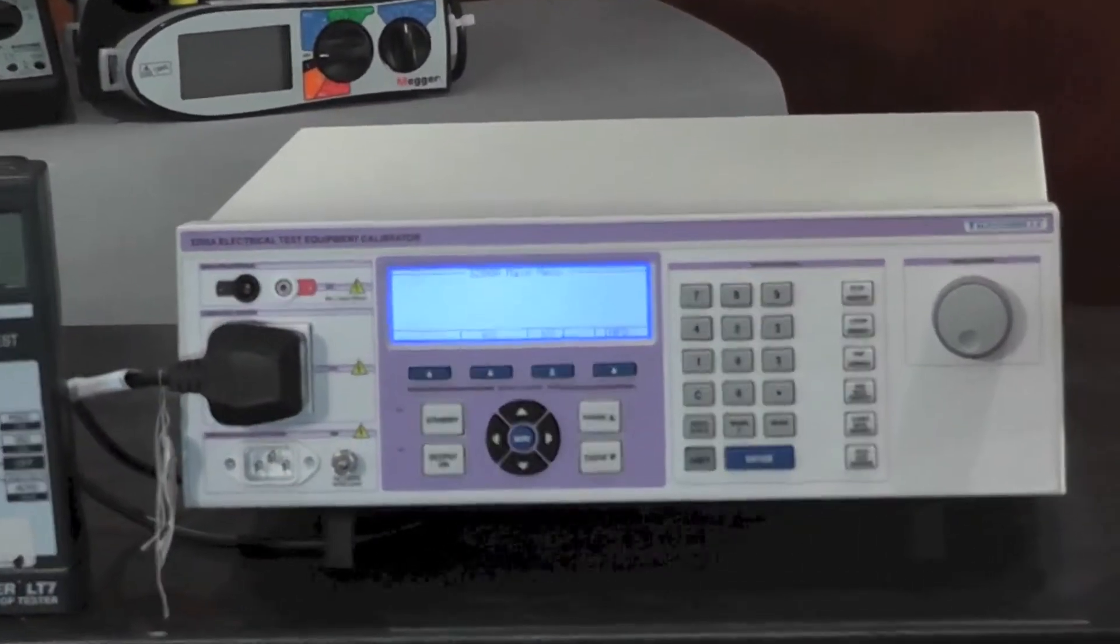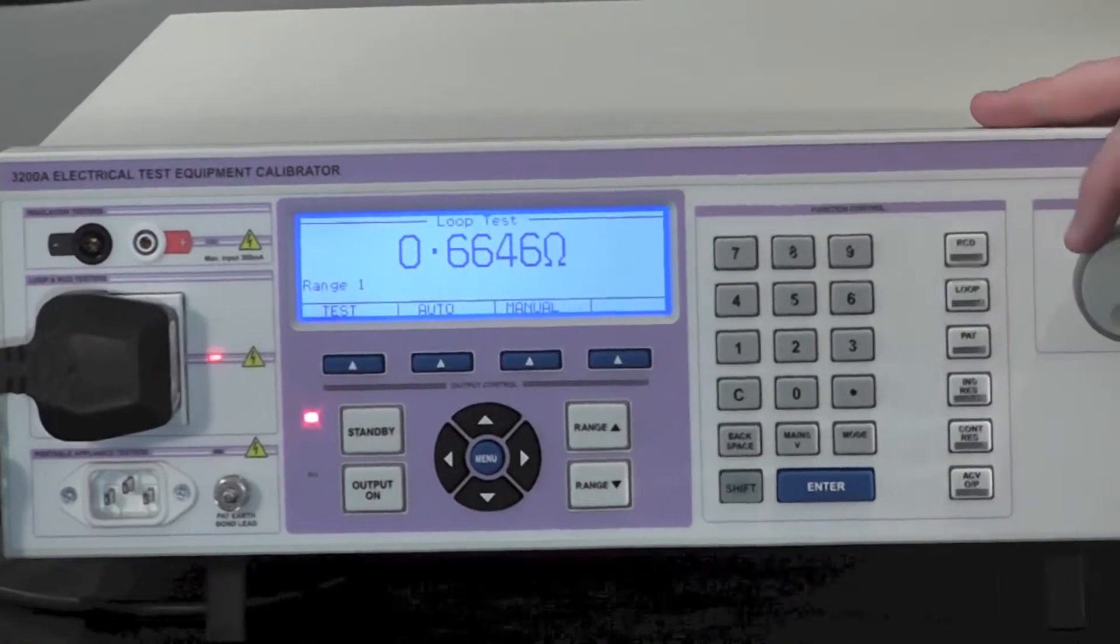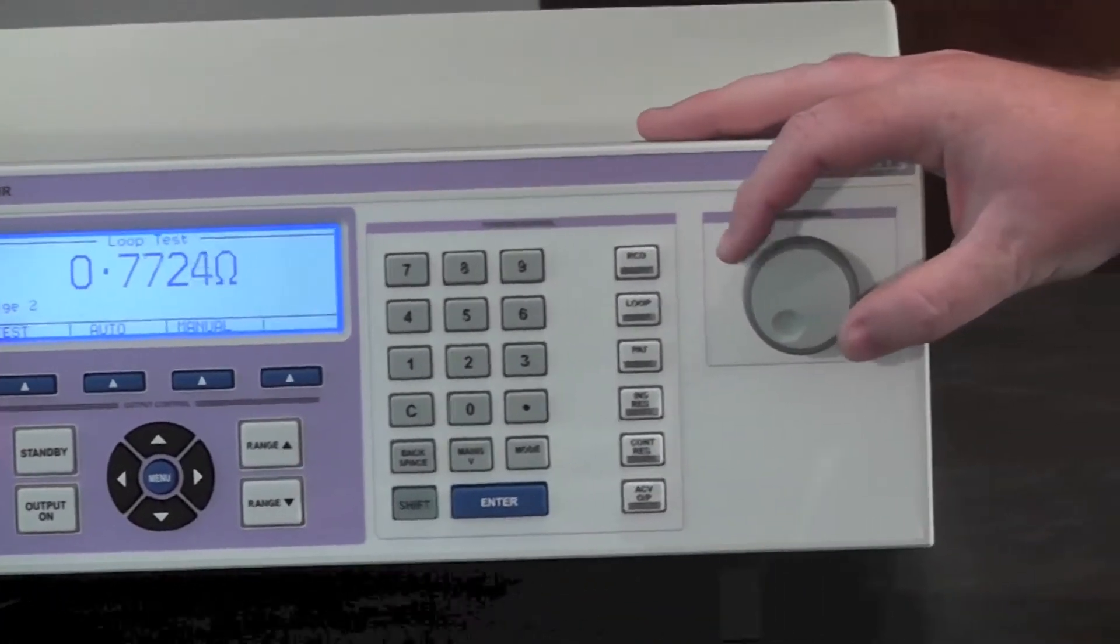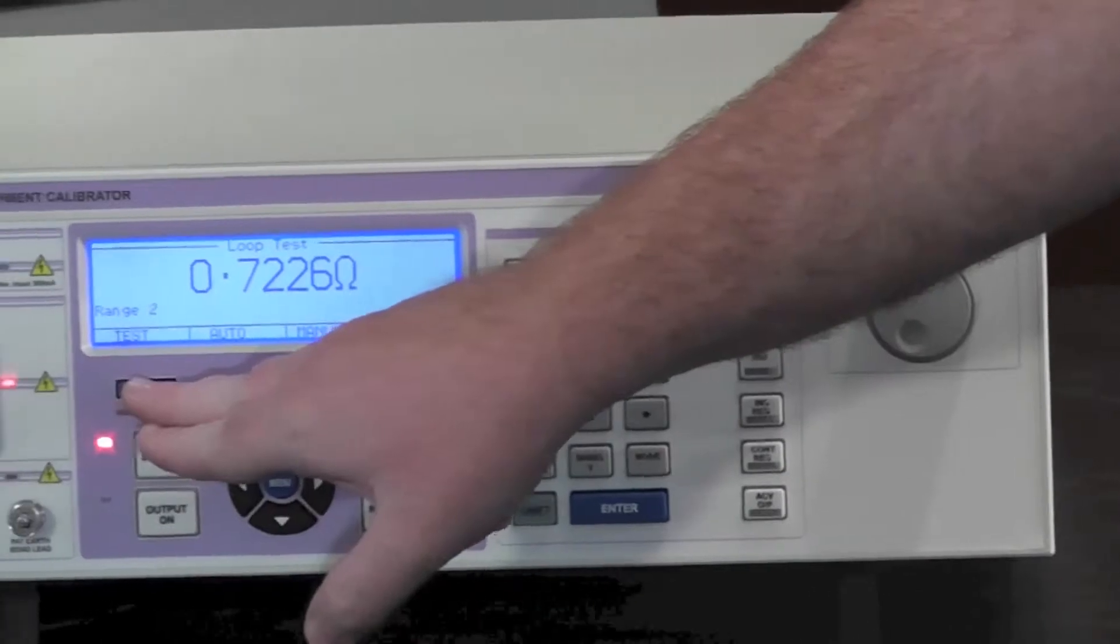To test a loop tester, press the loop key, select the range using the digital control and press test.